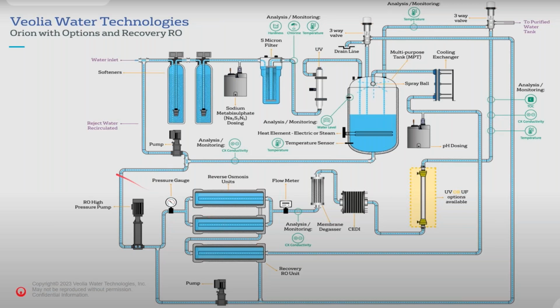Now, if we come into the more detailed nitty-gritty of the system of the Orion unit, as I say, its basis is softening, RO, EDI. So if we look at the inlet here, we're feeding with drinking water as a minimum, as per the guidelines. And there's two main things you have to remove before the water hits the RO and the EDI. One is you have to remove the hardness, and secondly any free chlorine in the feed water. And the way we remove the hardness is through softening.